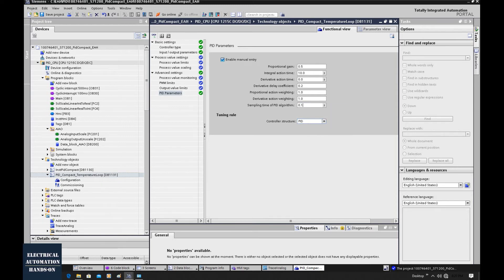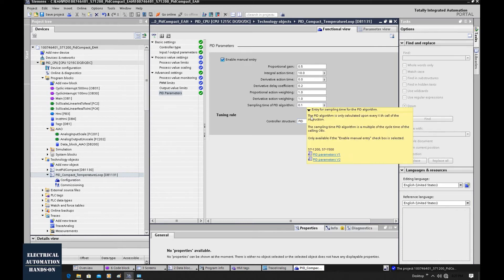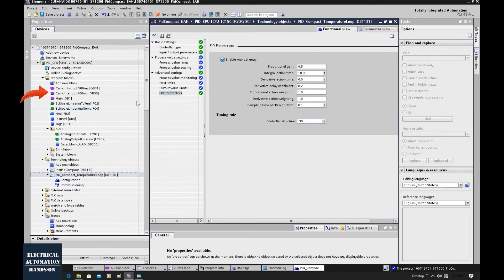We can also check the help here. The PID algorithm is only calculated upon every x calls of the instruction — the sampling time is a multiple of the cycle time of the calling OB. So our PID is called by this cyclic interrupt at 100 milliseconds. The minimum we can set is 0.1. We can also set 0.5, meaning every 5 calls this PID runs once, or 1 second, meaning every 10 times the interrupt calls this PID it runs once.